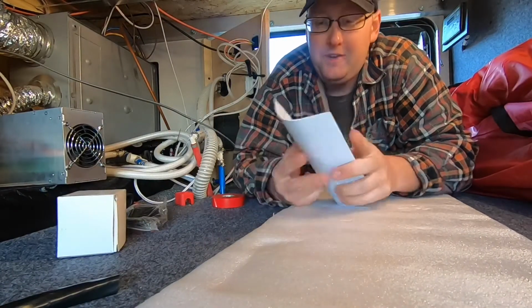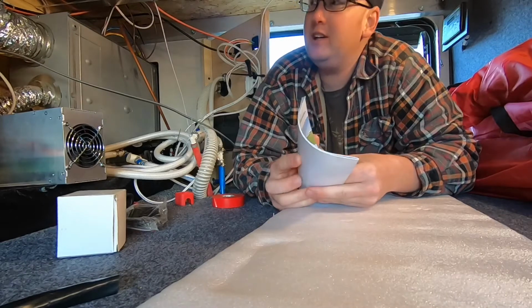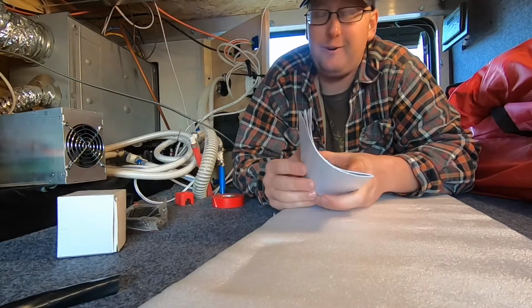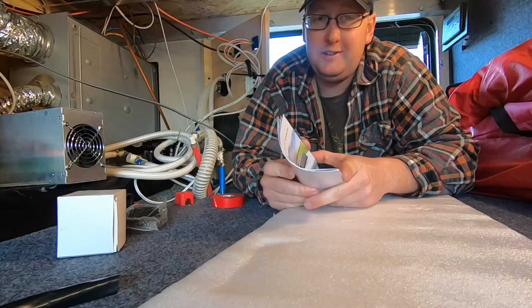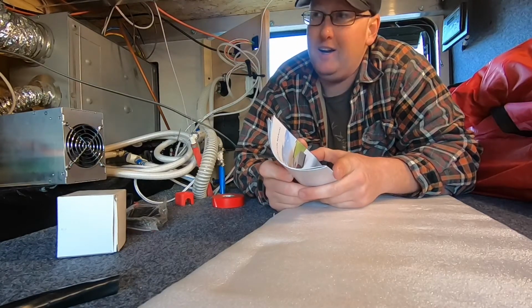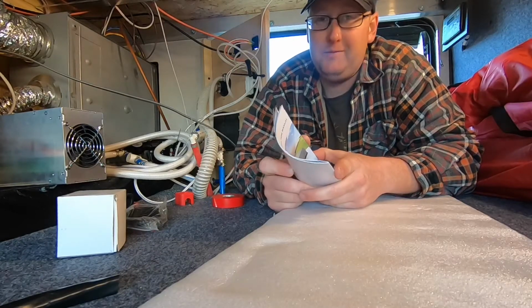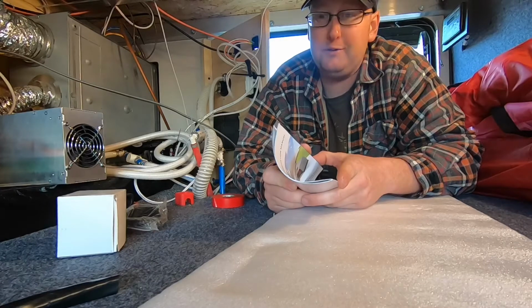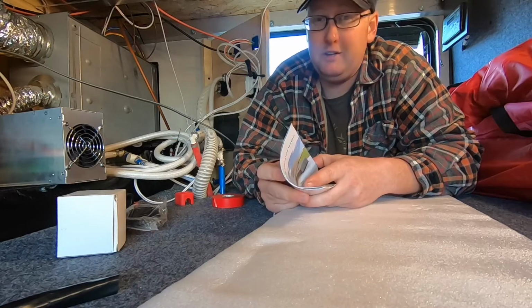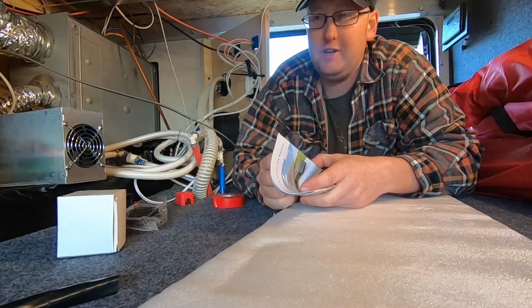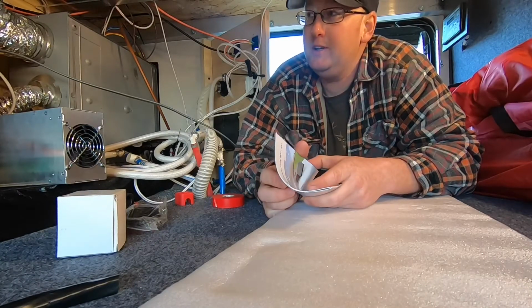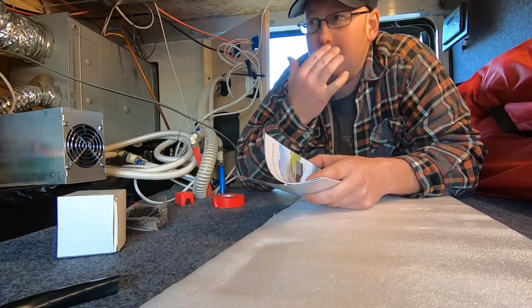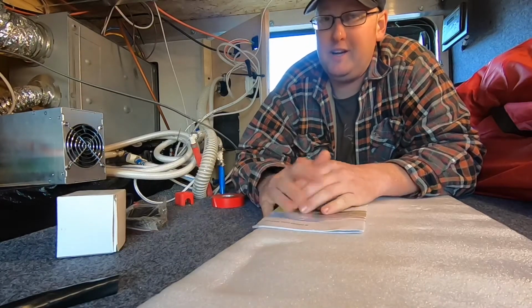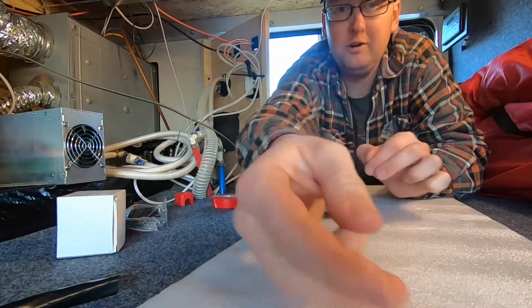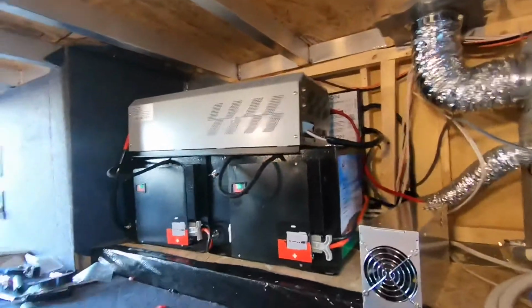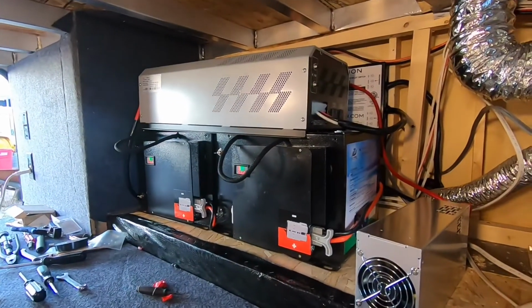So I have some good news and some bad news. The good news is I didn't fry anything. As horrible as that breaker sounded when I flipped it, somehow I was fast enough to shut it off before anything bad happened, and I did smell some electrical smoke. I went through and re-inspected everything, couldn't find anything bad, so I think I caught it just in time. I had an electrician come out and look over everything I did. He said everything was fine except for one error, and that's in the actual inverter itself.